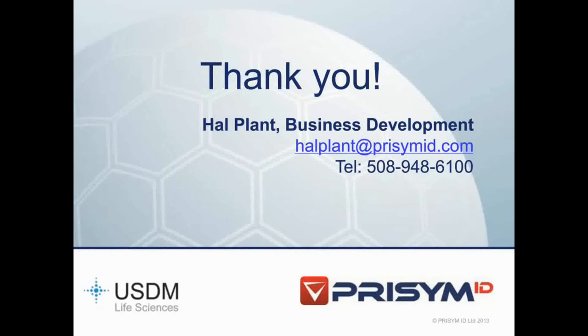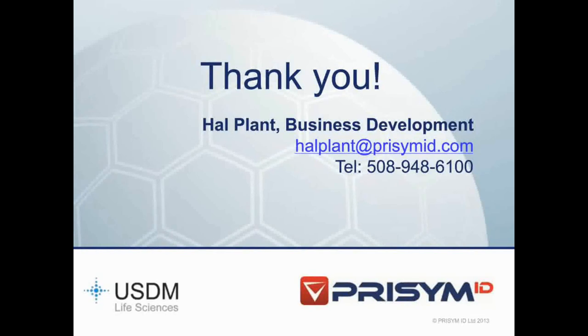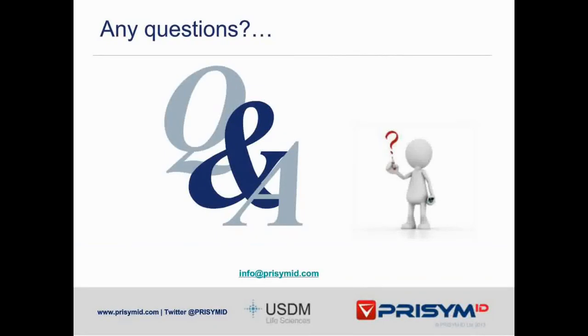The first question: can you clarify the human-readable aspect of the expiry date format for UDI? Great question — there is quite a bit of confusion between the standardized date format (four-digit year, dash, two-digit month, dash, two-digit day, per ISO 8601) and how dates appear in the human-readable portion of the UDI barcode versus elsewhere on the label.